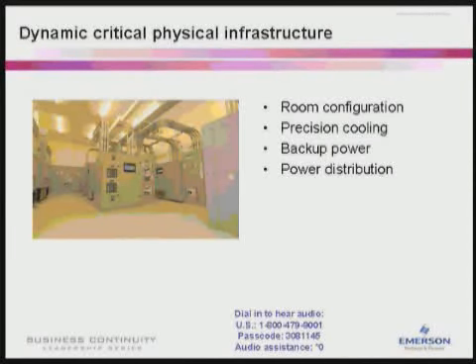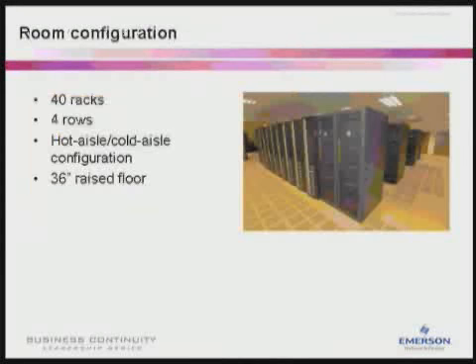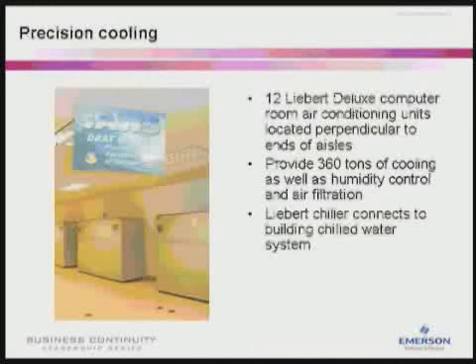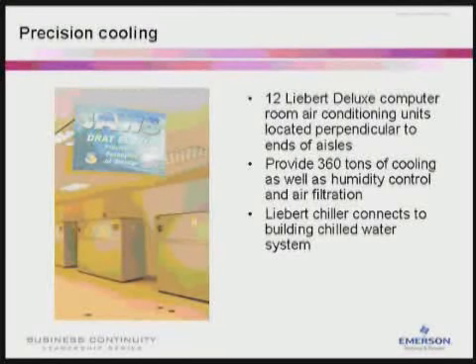Next slide. Our precision cooling consists basically of 12 Liebert Deluxe computer room air conditioning units located perpendicular to the ends of the aisles. It provides 360 tons of cooling, as well as humidity control and air filtration, which is a real critical element that those systems provide for us, and that's backed up by some Liebert chillers connected to the building chill water system. Next slide.